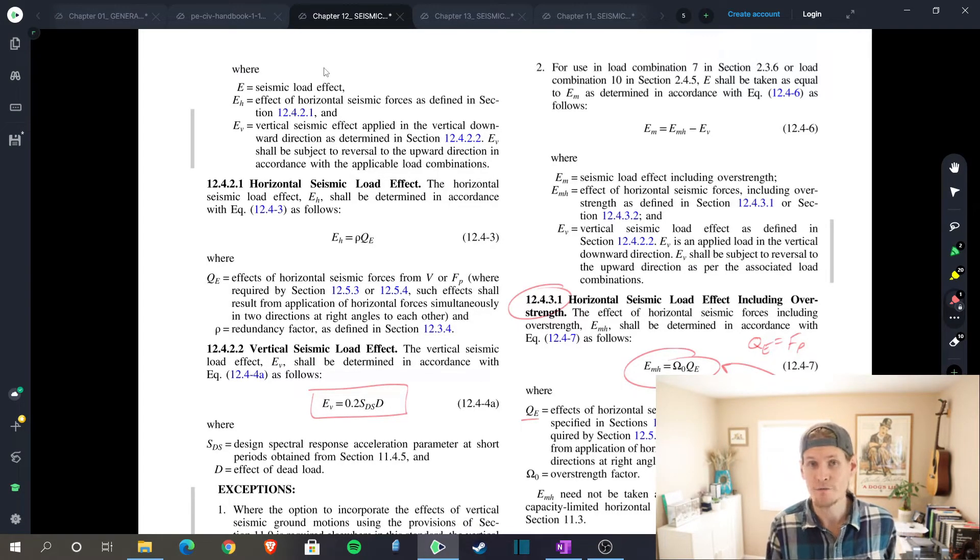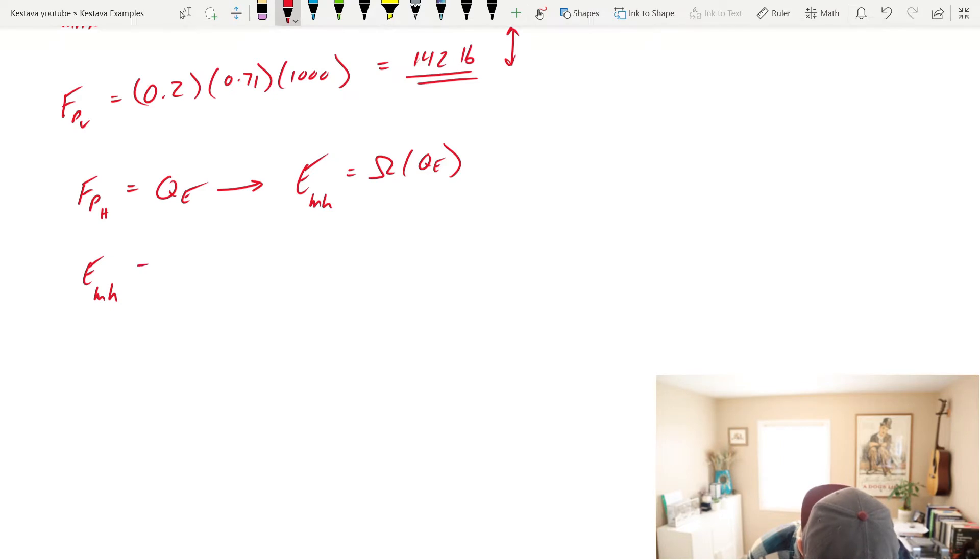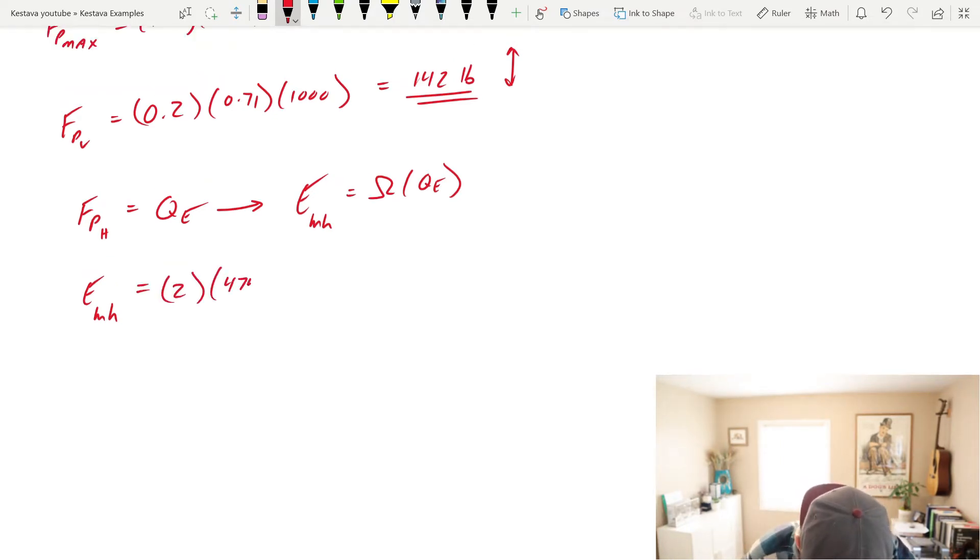EMH is equal to 2 times 474 pounds, which equals 948 pounds of horizontal force that we're designing for. So see how that got bumped up? Pretty significantly. We're going to box that out because that is one of our final forces. EV is just equal to FPV, which we already found is 142 pounds up and down. That we're also going to box.